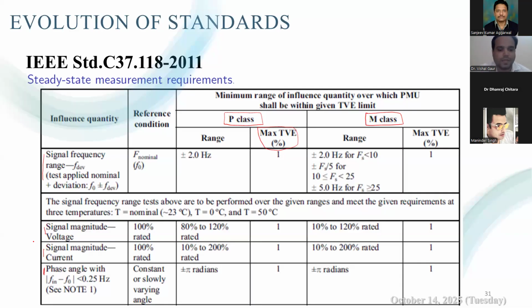So if you observe for the P class PMU, the maximum total vector error must remain within the limit of 1% when the frequency changes within the range of plus minus 2 hertz. So if the fundamental frequency is 50 hertz, and at any moment the frequency of the signal deviates by plus minus 2 hertz, or you can say the signal is between 48 to 52 hertz, then in such a case also the P class PMU must report the phasors with a maximum of 1% total vector error.